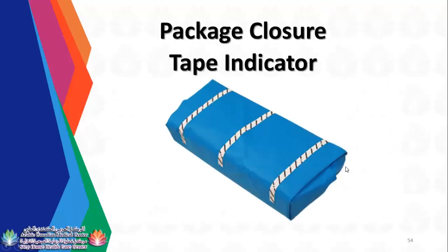Tape indicator, this is a sample of your tape indicator. It will change to black once it is exposed to steam. So you need to check, for example, because I don't have the image here, you place the tape here, okay? You need to check if the tape indicator is not broken. If the tape indicator is not broken, then they can use it. If it is broken, then they cannot use it.